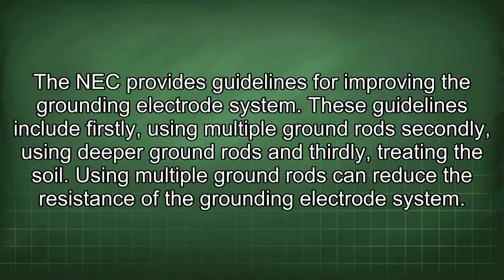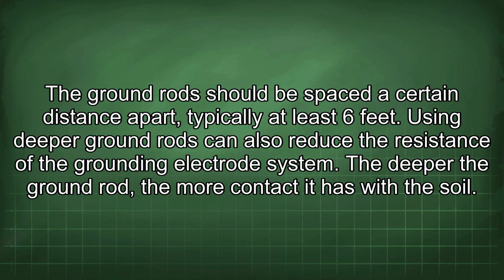Using multiple ground rods can reduce the resistance of the grounding electrode system. The ground rods should be spaced a certain distance apart, typically at least 6 feet. Using deeper ground rods can also reduce the resistance of the grounding electrode system. The deeper the ground rod, the more contact it has with the soil.